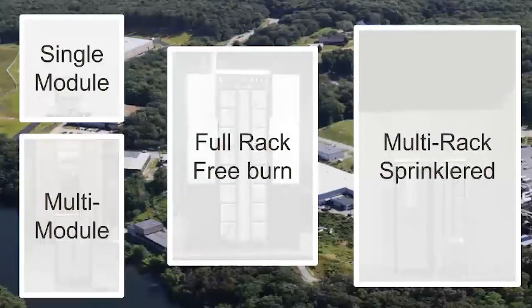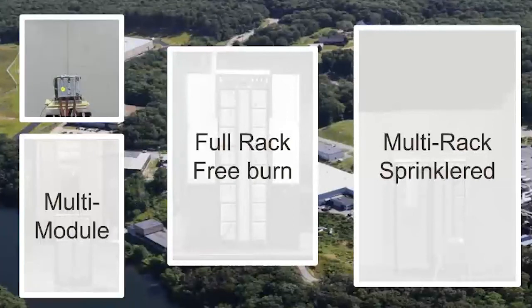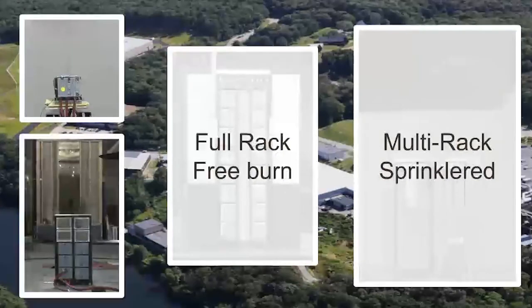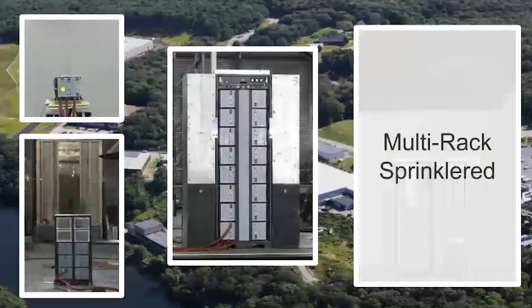Okay, so we ran testing starting at the single module level, and based on that, we had single module, then we went to multiple modules, and then from multiple modules we moved up to full-scale rack storage fires, and that's all done in free burn. That's really to try to assess the impact of scale on the fire, going from a single module all the way up to a full rack.